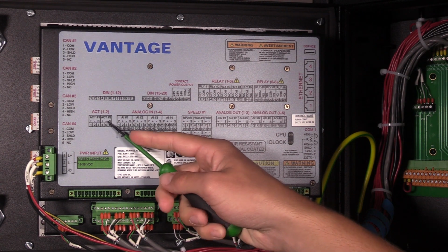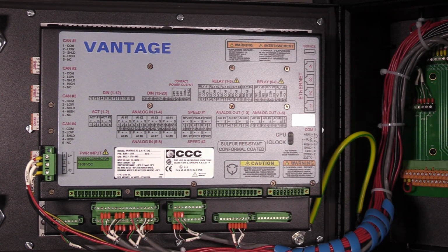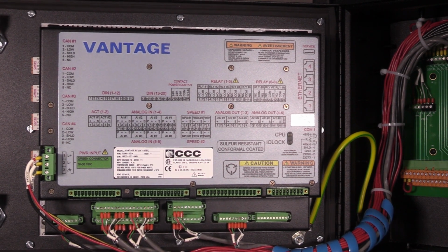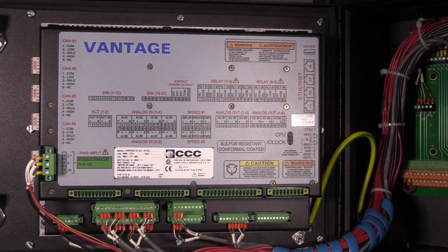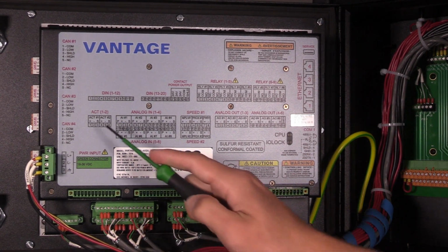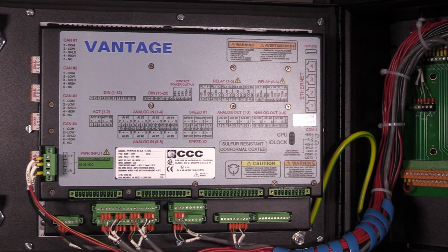The final type of signal wiring we'll discuss is driver or actuator outputs. Each driver can be configured for low-range 20 mA or high-range 200 mA operation. The actuator output signal requires a twisted shielded pair cable for wiring. It should be wired as follows.